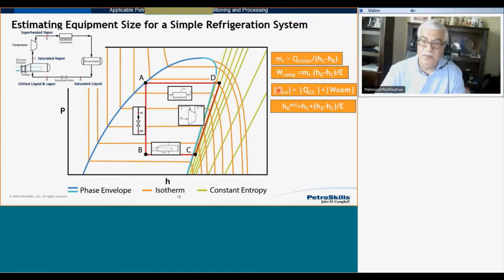That gives me the condenser duty. And I can calculate the actual discharge temperature if I want to by calculating HD actual using this equation. I know all the terms on the right-hand side. So I get HD actual, I know the discharge pressure or condensing pressure, so I can determine the actual discharge temperature as well.